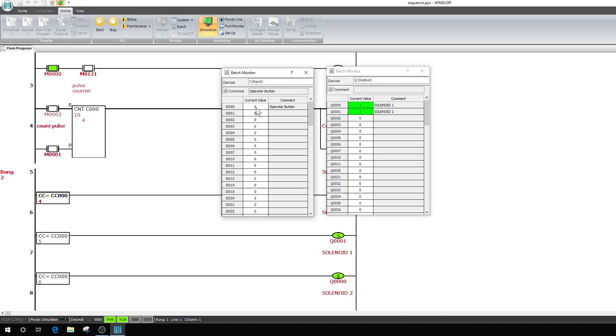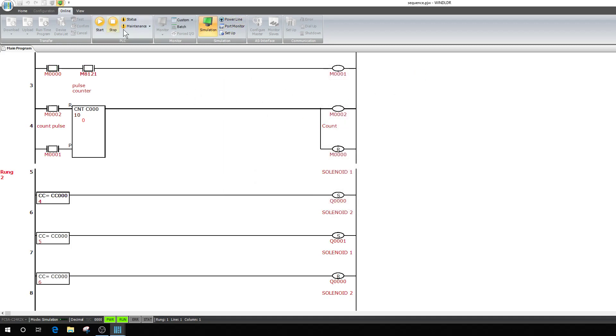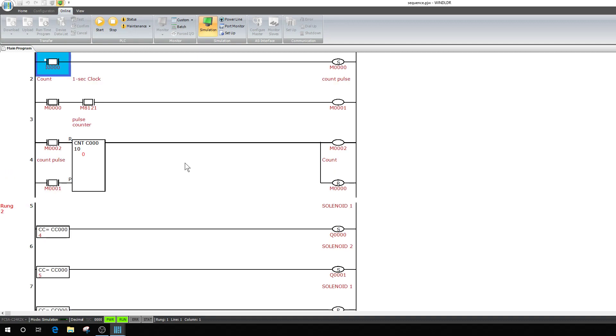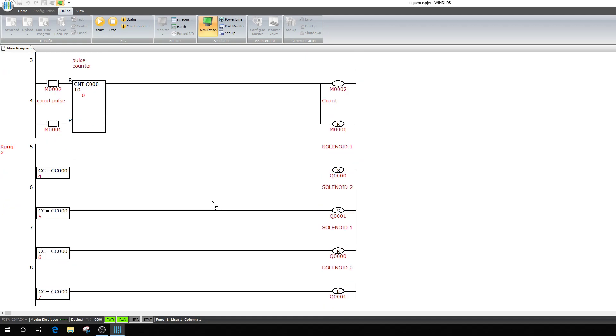In the Batch View, if the display looks off you can click the check mark to show comments out here. I'll grab another batch view and pull up my outputs. If it shows the full word you can click that and it'll put it in the comments. It gives you the actual current value and state. You can use this in monitor mode — not just simulation — if you want to see inputs and outputs going on and off inside your PLC for diagnostics.